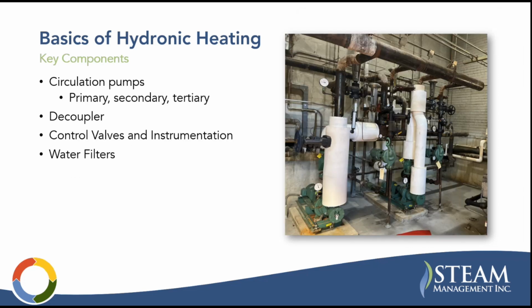You have circulation pumps. Those can be primary, secondary, or tertiary pumps. We'll talk more specifically about those later. You have a decoupler, which applies to primary-secondary systems. So you don't always have that, but we'll talk about that later as well. Control valves and instrumentation. You can have water filters, and they're recommended. You can have a full system water filter where it takes the full flow of the system, or you can have a slipstream filter where maybe it takes 10% of the flow and filters the water over time.